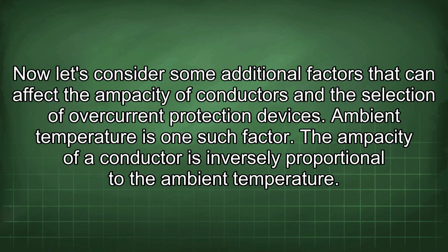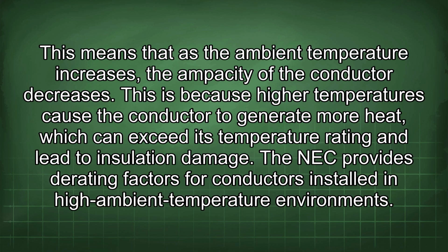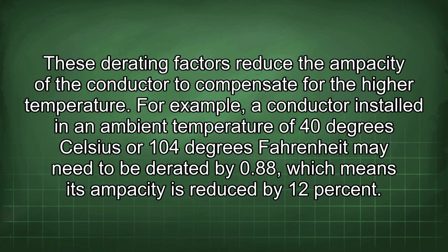Now let's consider some additional factors that can affect the ampacity of conductors and the selection of overcurrent protection devices. Ambient temperature is one such factor. The ampacity of a conductor is inversely proportional to the ambient temperature. This means that as the ambient temperature increases, the ampacity of the conductor decreases. This is because higher temperatures cause the conductor to generate more heat, which can exceed its temperature rating and lead to insulation damage. The NEC provides derating factors for conductors installed in high ambient temperature environments. These derating factors reduce the ampacity of the conductor to compensate for the higher temperature. For example, a conductor installed in an ambient temperature of 40 degrees Celsius or 104 degrees Fahrenheit may need to be derated by 0.88, which means its ampacity is reduced by 12%.